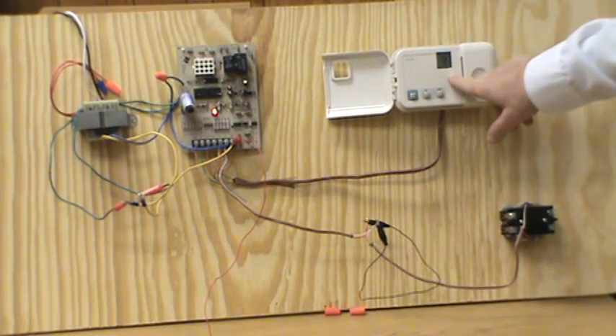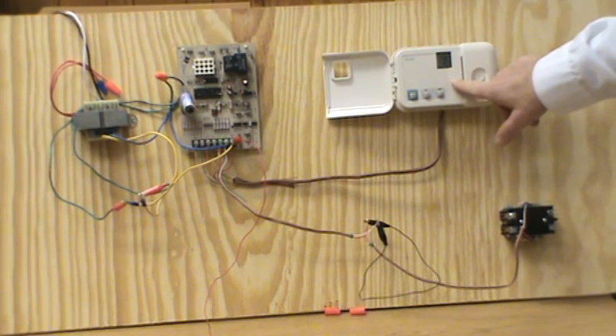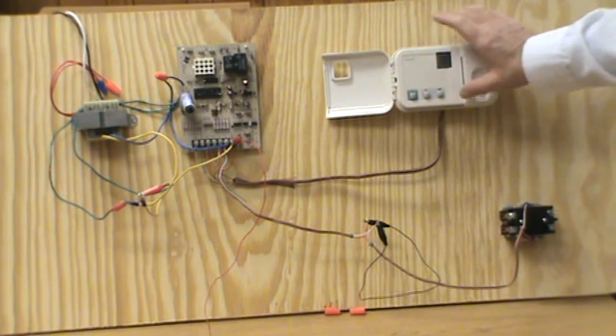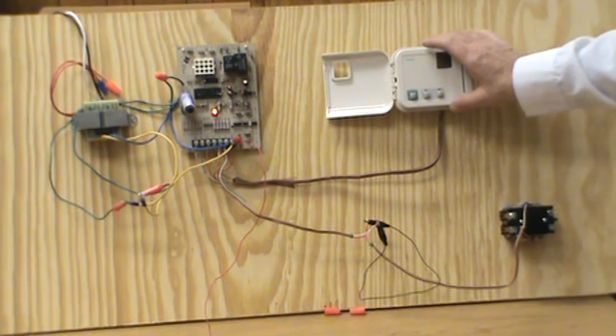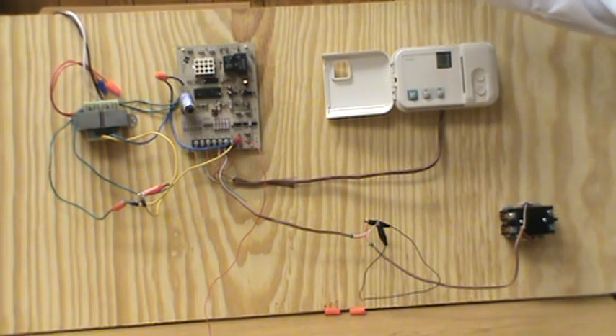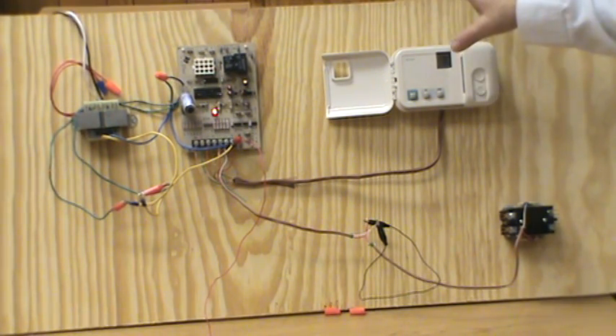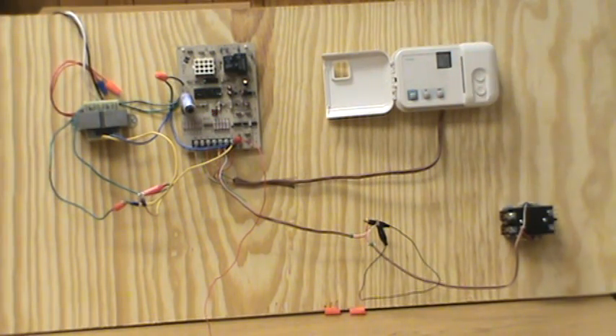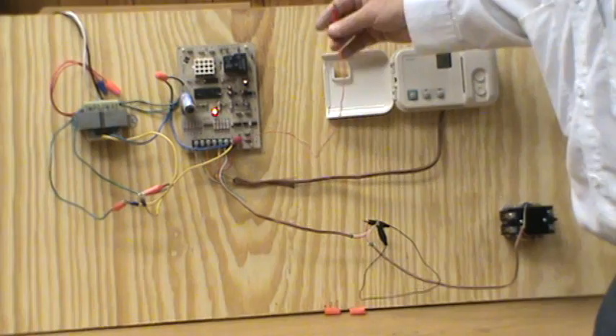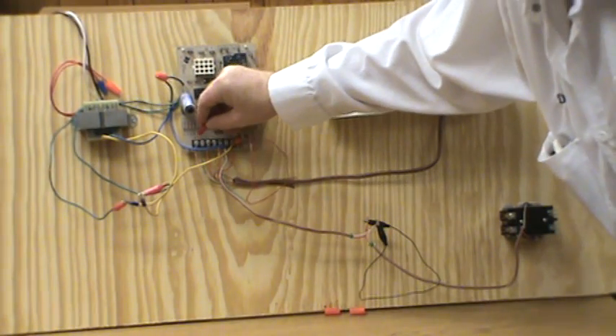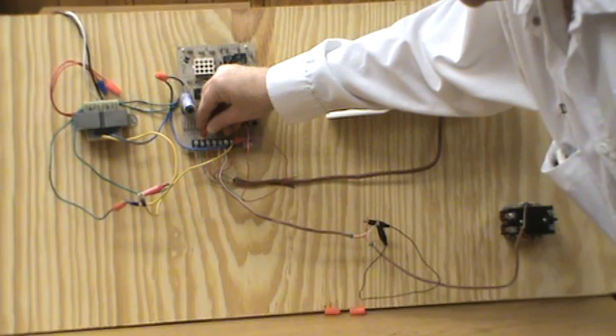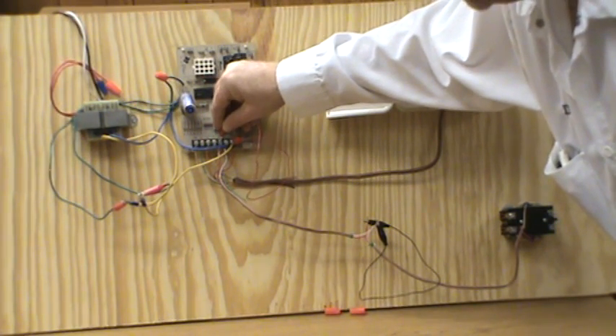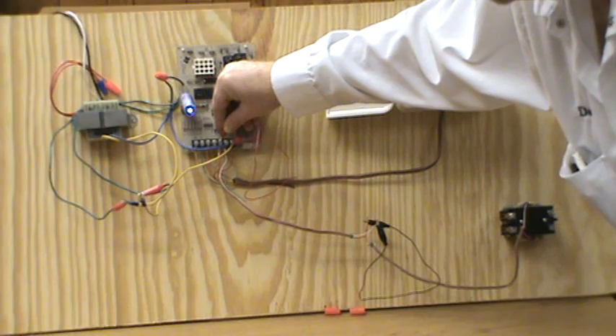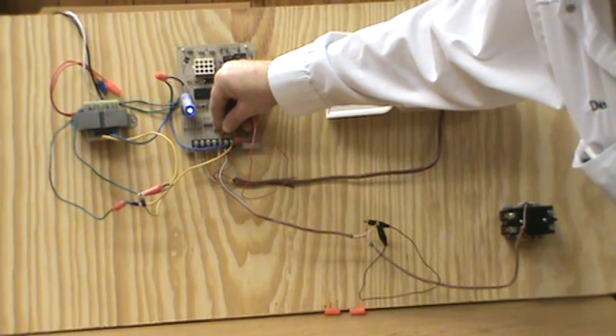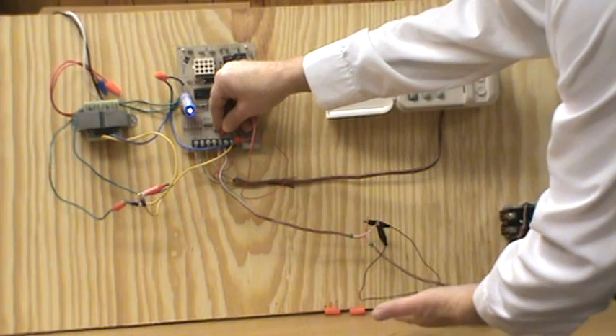And it talks about leave the thermostat in the off position for the mode and the fan and the automatic, because a lot of these digital thermostats, when you power it up, there's a 5-minute delay. You've wasted 5 minutes already. So leave that in the off position, and now we're ready to look for a short. We'll take the red jumper lead and we'll hit each branch circuit till we hit, there you go, there's the cooling circuit. That's the one we've got the short on the wiring going out to the condenser.